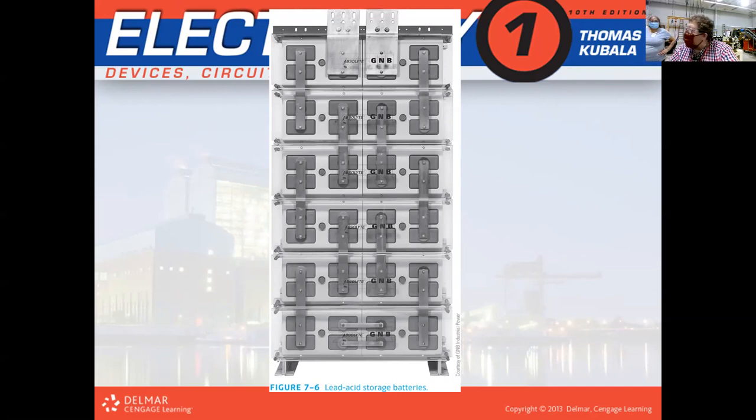I used to have an operator come up to me in the morning and say, my forklift won't run and I had it plugged up all night long. And I said, did you put water in it before you plugged it in? Well, no, I didn't check it. So I start opening up cells and find the water's below the dividers in the cells. If it's like that, it's not going to charge up. So that's another thing on those that have to have water in it, to keep the electrolyte up high.